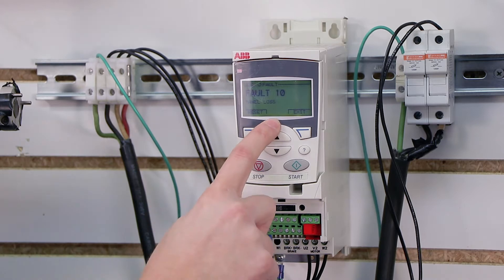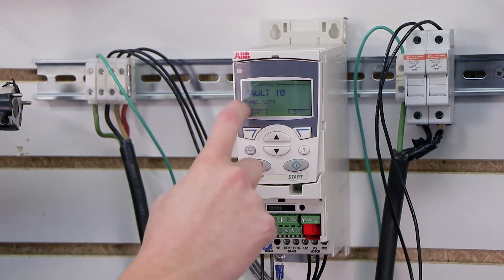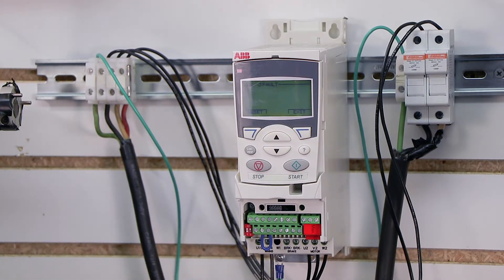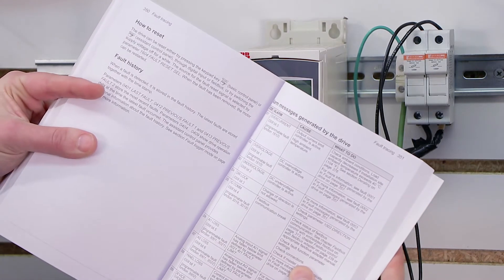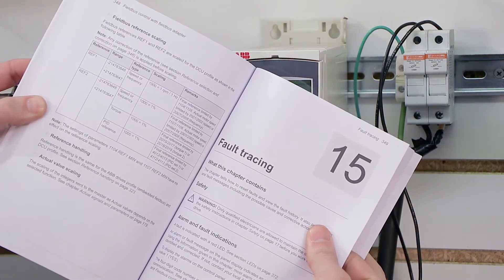Now anytime you experience a fault on the ACS355 series drive, it is going to tell you a fault code, the name of the fault, and a brief description. But most of your work is actually going to be done right here in the manual. They have a really nice, well-detailed section called fault tracing.